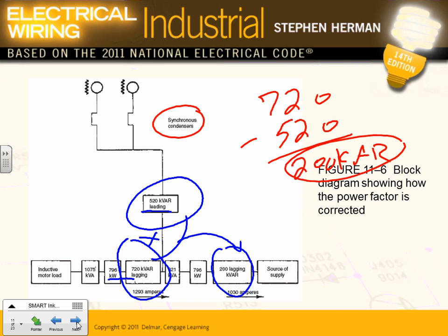When you get the spinning, and you put DC into the synchronous motor, by design, the magic of it, it starts kicking back VARs, adjusting your power factor. We'll get into the guts of how it works, but I'm interested more in this: guys, if you have a synchronous motor giving you this amount, it will knock down the VAR in your building.